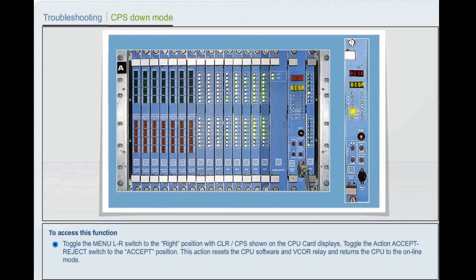Toggle the action Accept Reject switch to the Accept position. This action resets the CPU software and vital cutoff relay and returns the CPU to the online mode.